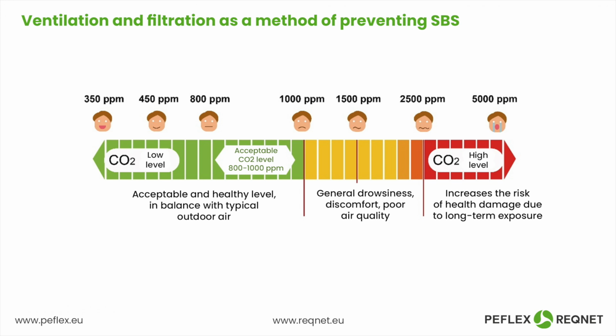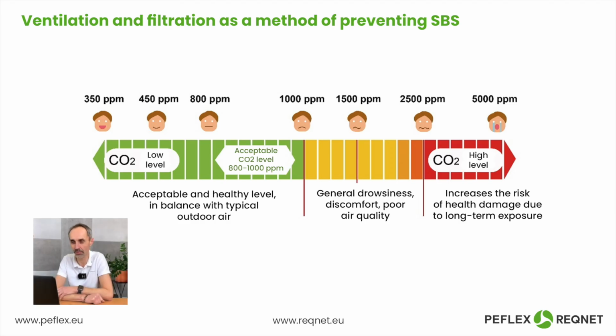the primary and overriding goal of a ventilation system is to remove excess, or to maintain proper air quality in terms of carbon dioxide concentration, that is, to keep it within the range from background levels, where the background is between 350 and 450 ppm of carbon dioxide, up to parameters of 1000, 1200 ppm. This value is kind of a borderline value, depending on the institute that conducted the research. But let's assume that the optimal carbon dioxide concentration, which does not affect us, people, in any way, is exactly that 1000 ppm.